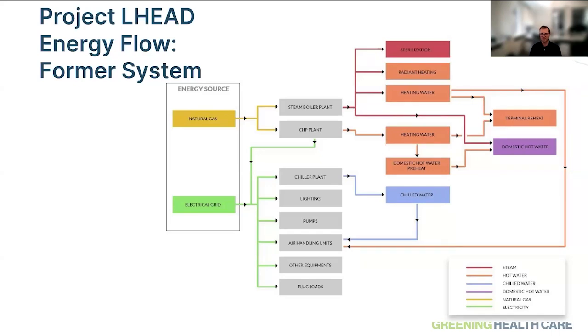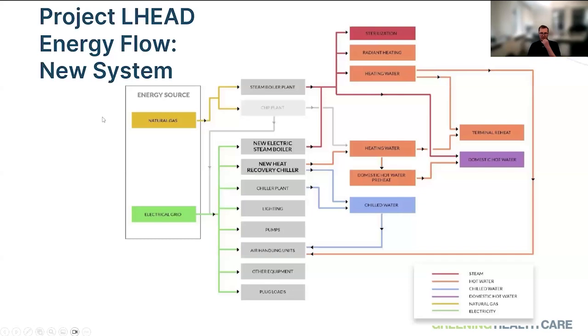So your ventilation systems, your plug loads, lighting, chiller plant to do the cooling, all of these, various electrical loads. And these two systems operate completely independently. At Lake Ridge, there's a cogen plant, so there's a bit of interconnection between electrical and natural gas, but generally they operate completely disconnected. And so a heat recovery chiller, I think on the next slide, is kind of an opportunity to tie the two together.